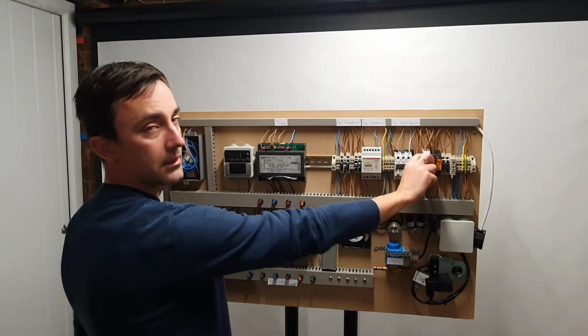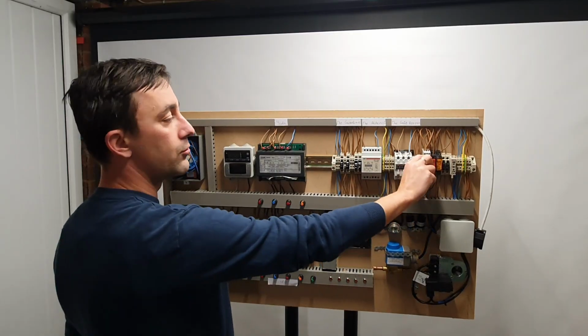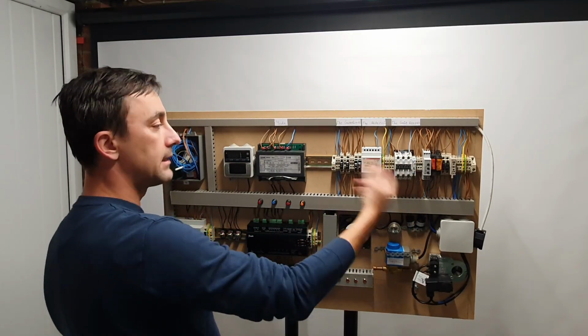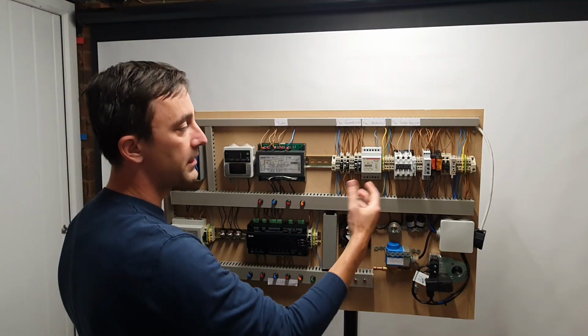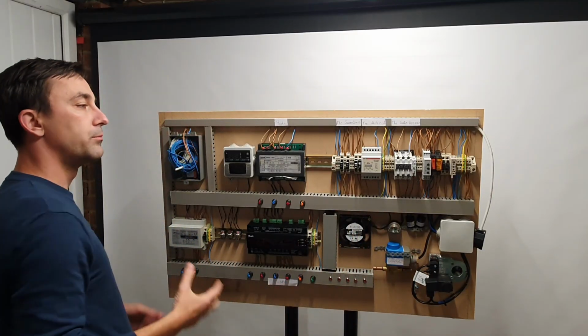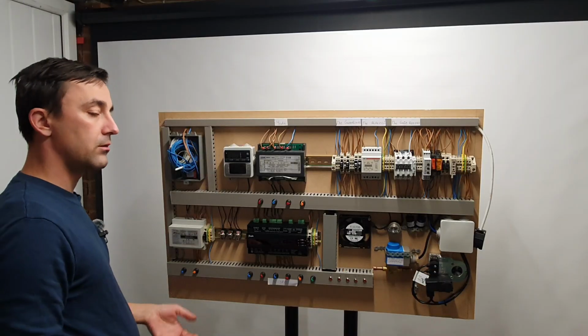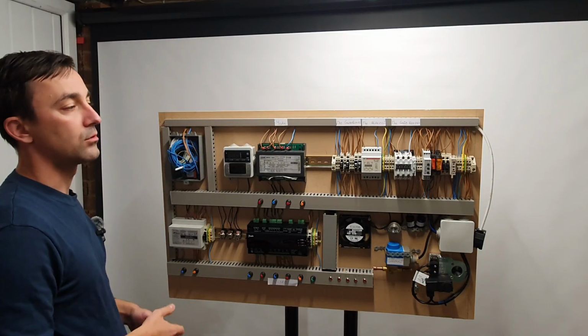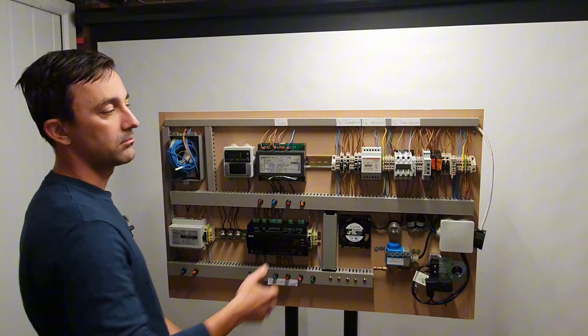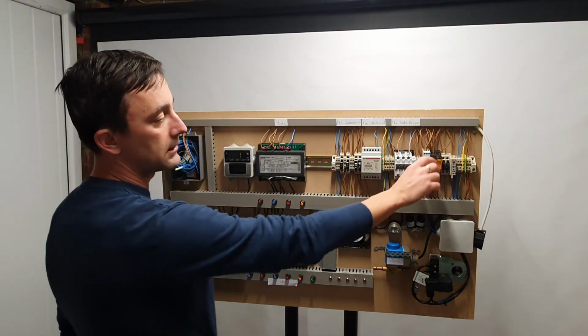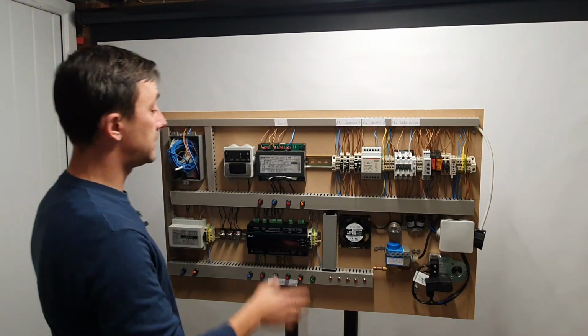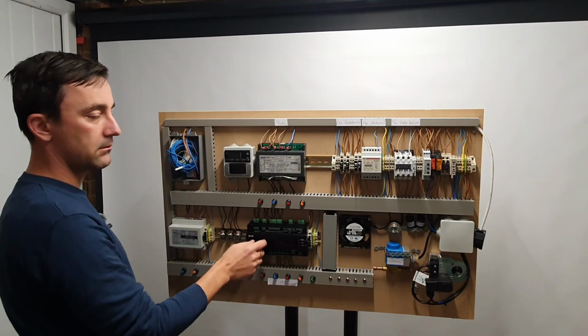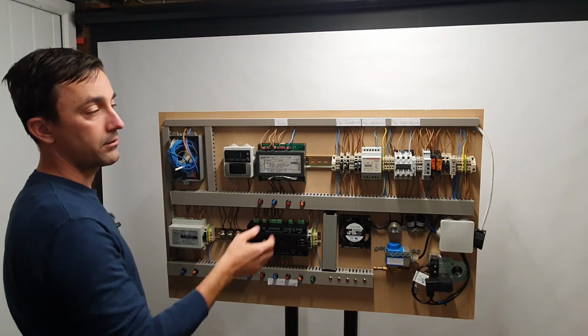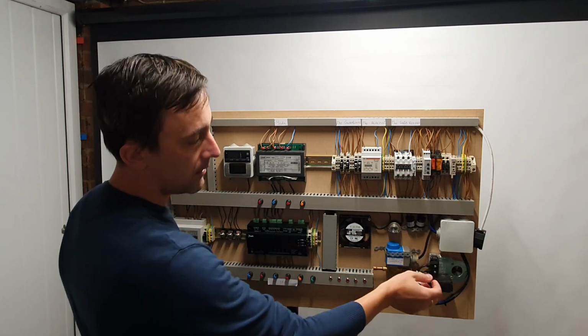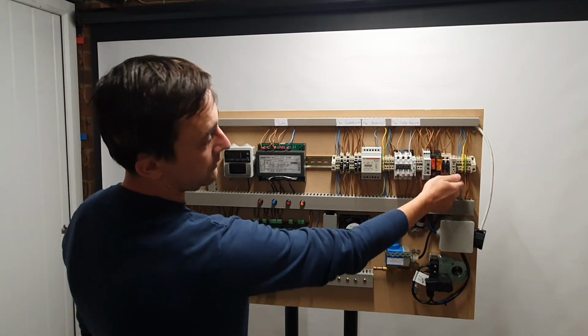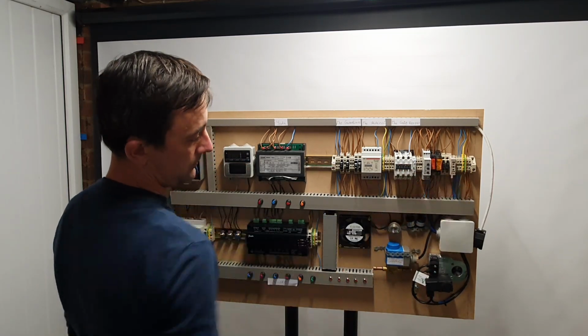We've got a timer relay, which is used to bring on the second compressor. That's because you don't want to bring on 2 compressors at once. It would pull too many amps and it would cause a few problems. So we tend to find a timer relay in place. Sometimes it can be done by the controller itself. I decided to put a timer relay. Yeah, we've got some more fuses. We've got our compressor fuse, which is this one.